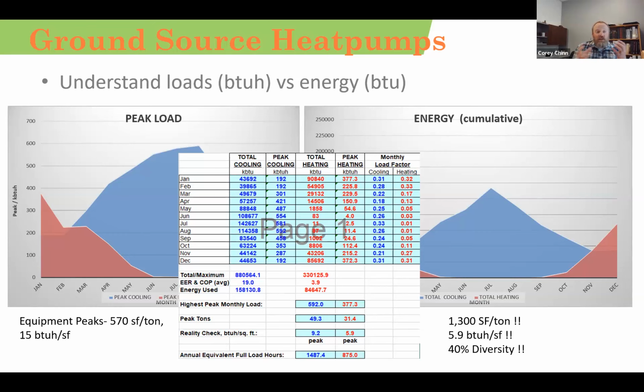So when folks are looking at traditional systems versus geothermal, we have to help them understand the difference in how we are able to share heat around the building and how that impacts the sizing of our total heat rejection and heat absorption that we need from the ground, because the sizing of our ground loop is not equivalent to the sizing of a traditional air-cooled or gas-heated system. So these values, if you sized a chiller and a boiler at this, you would not be able to accomplish thermal comfort, I can assure you.